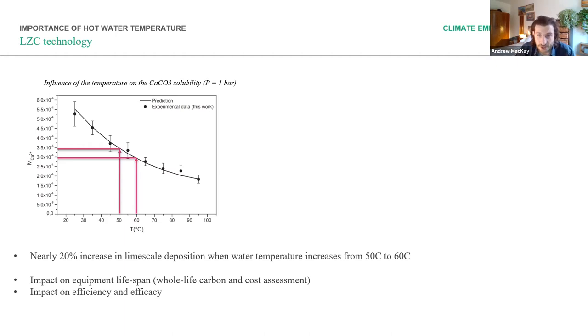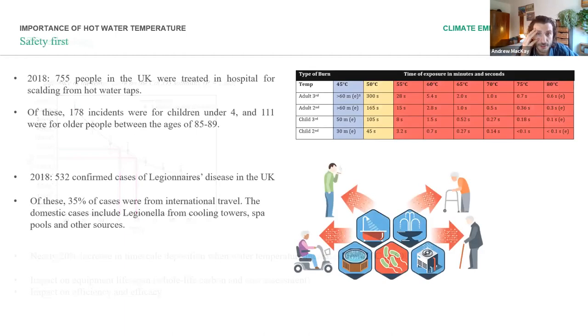So the lifetime of your HIU goes down, your TMVs inside apartments, along with the other plate heat exchangers that you've got elsewhere in the heat network, require more maintenance. All of that adds up, but at the same time, you also get a reduction in performance across plate heat exchangers and also on your heat generating equipment, whether that's a heat pump or something else. So we skip on.